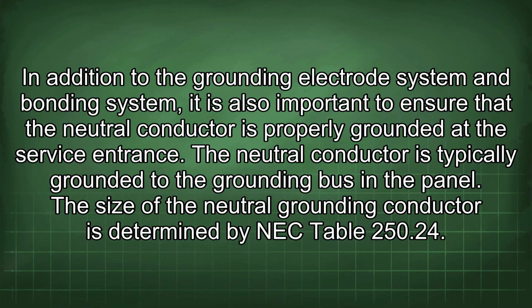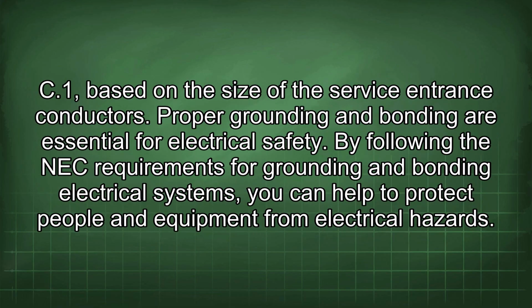The neutral conductor is typically grounded to the grounding bus in the panel. The size of the neutral grounding conductor is determined by NEC Table 250.24.(C)(1), based on the size of the service entrance conductors. Proper grounding and bonding are essential for electrical safety.